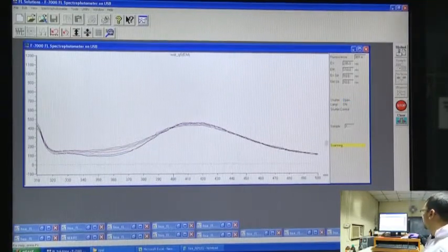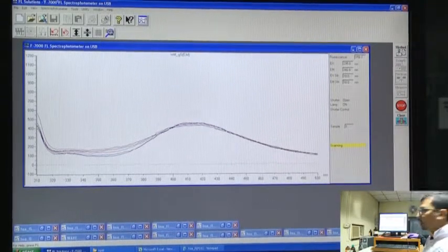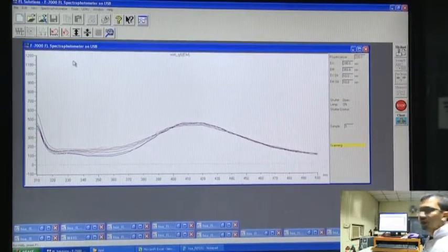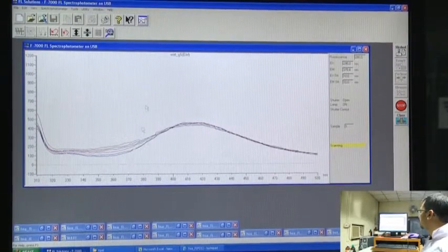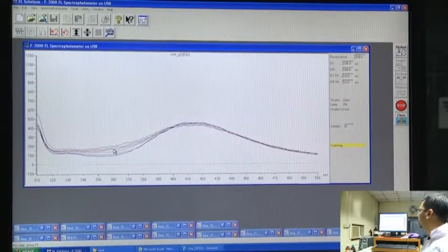One important thing while doing this fluorescence experiment is that while scanning is going on, make sure not to touch other parts of this instrument, like in this option do not try to click on these things. Okay. Why? Because once the instrument is running, clicking on other icons might affect this measurement. However, if for some reason you think that you have clicked the wrong icon, or the spectra is not correct, or you have serious reason to abort this reading, you can click stop directly out here. Do not click this cross icon while the spectrum scan is going on.